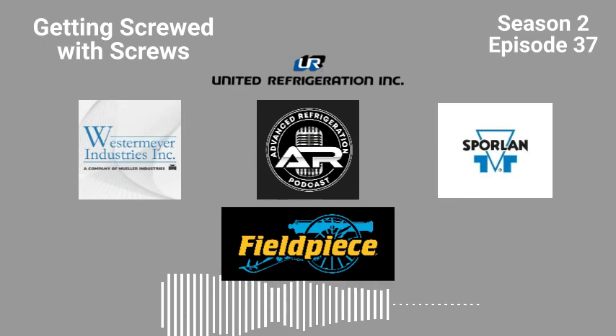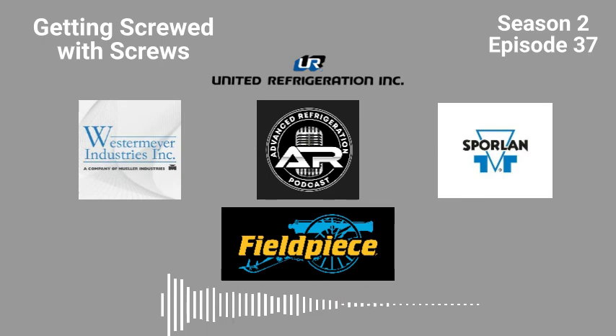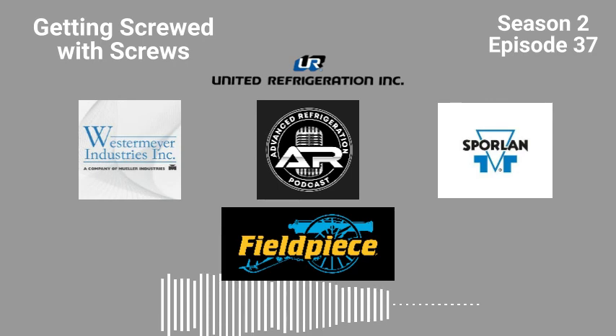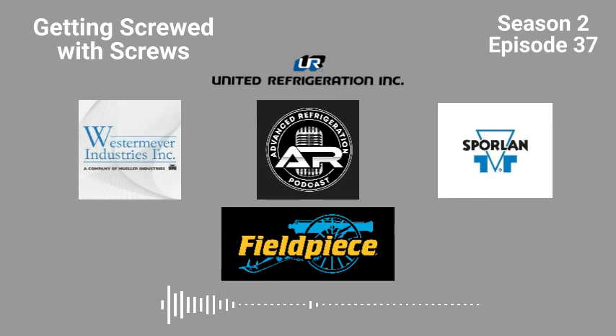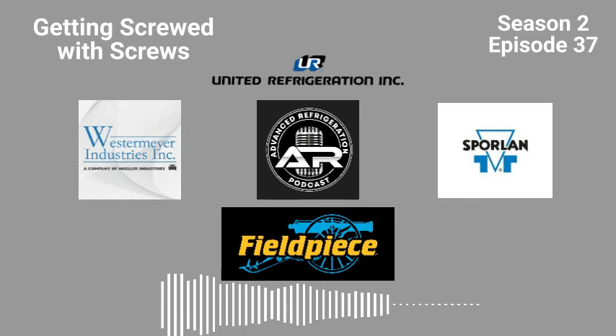So as soon as I started pushing the programs back to them, from the white wire for your signal to black, I would have no voltage, 0 volts. If I pulled the white wire off the controller and went to black, I would have 1.8 volts, which is exactly what it should have had. As soon as I pushed the program back down to these, they all started working. And I had the 1.8 volts that I should have had on the white wire for the transducer for the PB5.